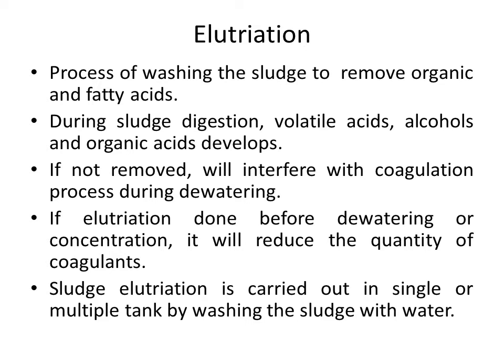During de-watering, coagulants cause solid parts to settle at the bottom so water can be removed from the sludge. We must remove volatile acids, alcohols, and organic acids so they do not interfere with coagulation. If elutriation is done before de-watering or concentration, it reduces the quantity of coagulants needed. Sludge elutriation is carried out in either a single tank or multiple tanks by washing the sludge with water.